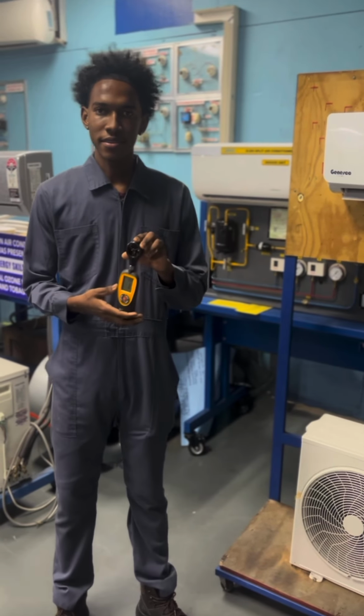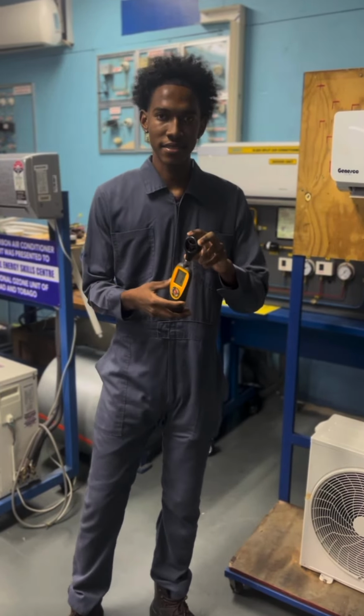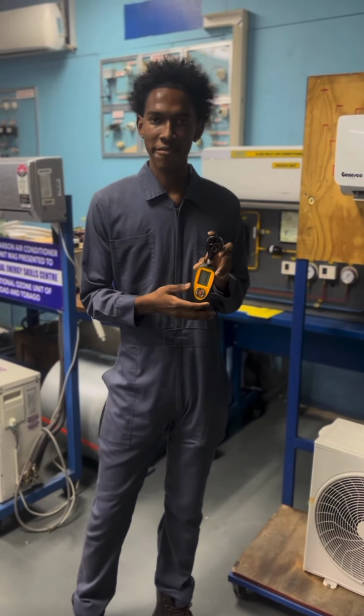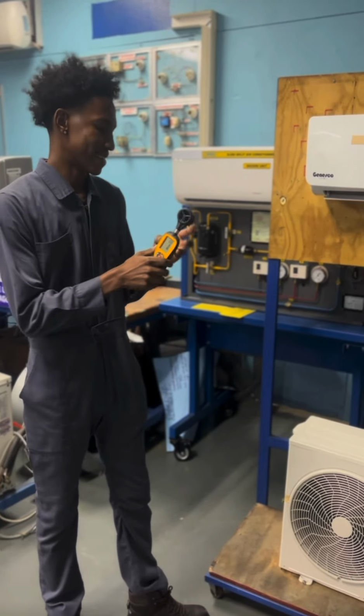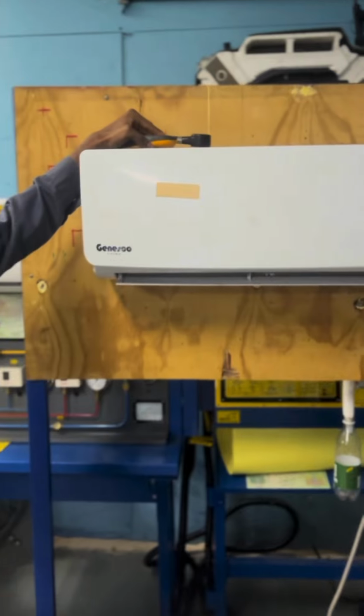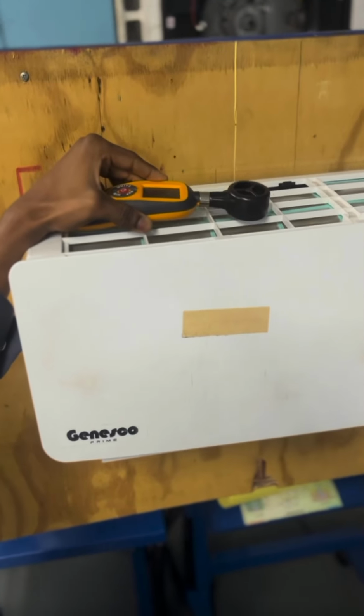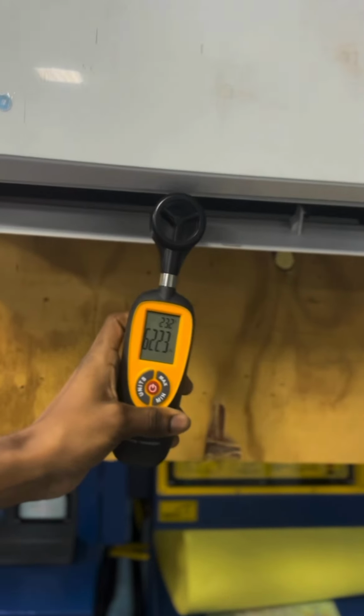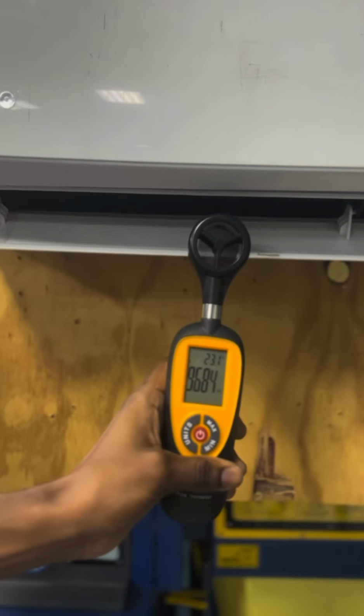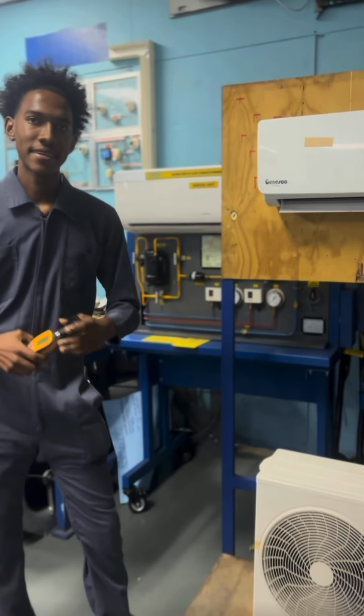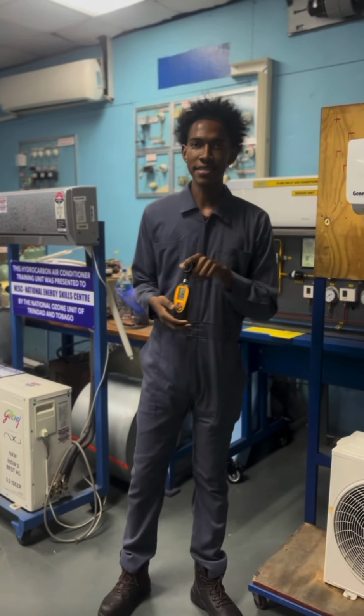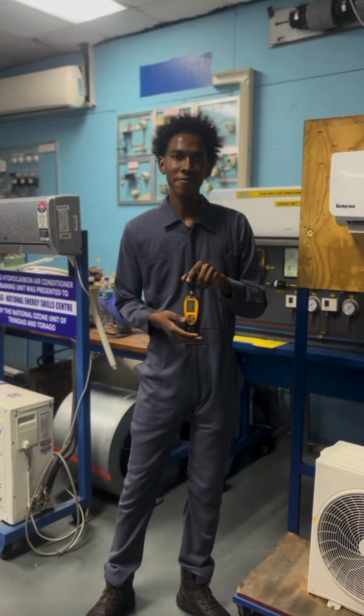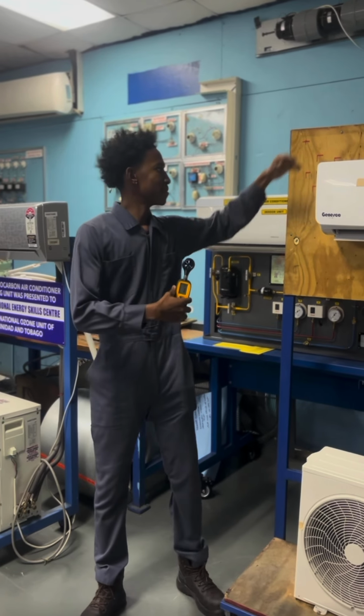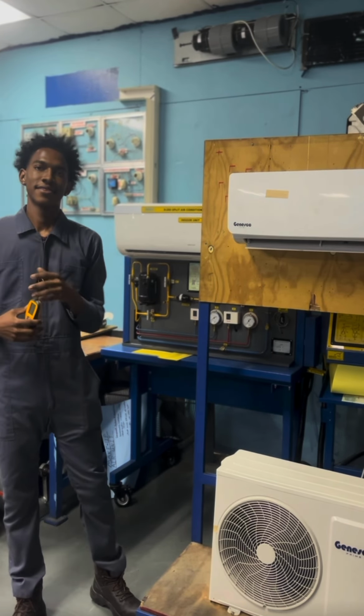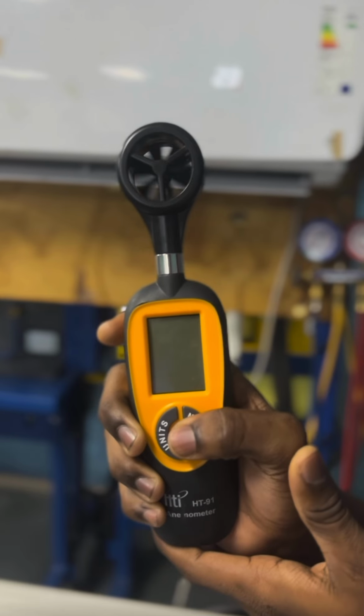A simple use of an anemometer on a split air conditioning unit is to measure CFM, right? So you're calculating the return air, right? Then the supply air, right? In order to calculate these values accurately, you must have at least 4 inches of space from the ceiling to the unit. How to use an anemometer, step by step.